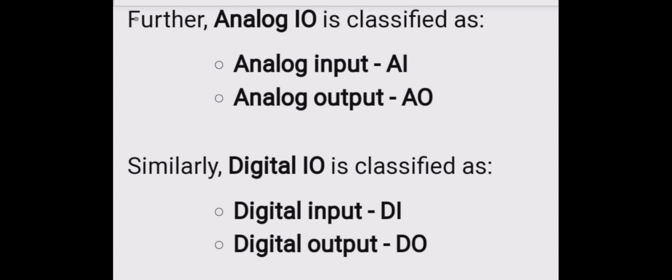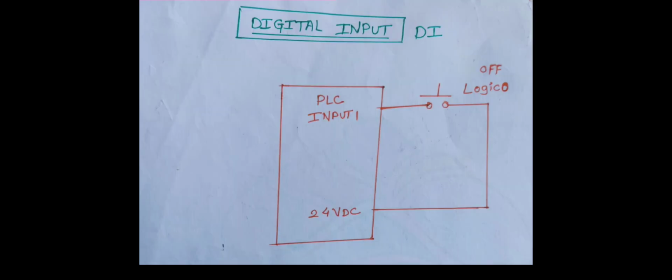So the short form of digital input is DI. The digital input is a circuit designed to receive the binary signal transmitted from industrial sensors and translate that input into a reliable logic signal for the PLC, in any industrial controller. So it is used in the PLC and motor drives to receive the 24-volt digital input from the field sensors and switches.